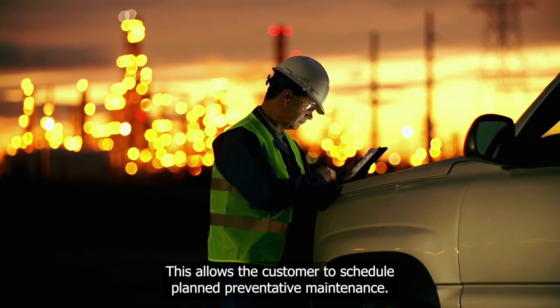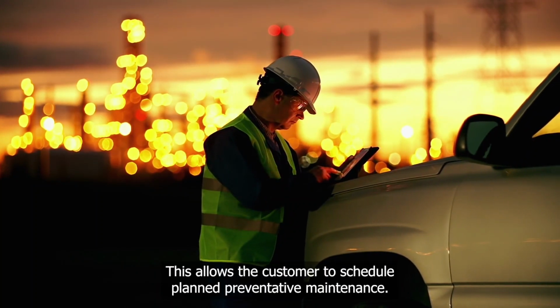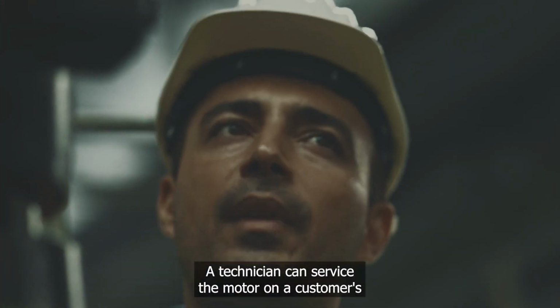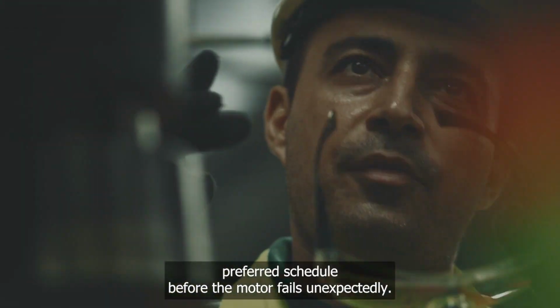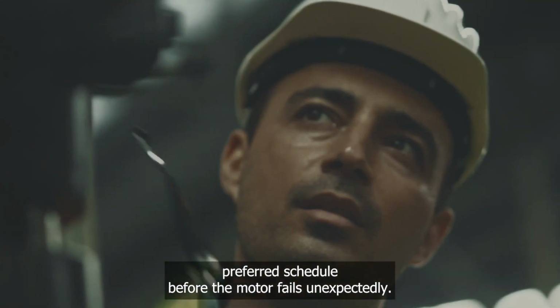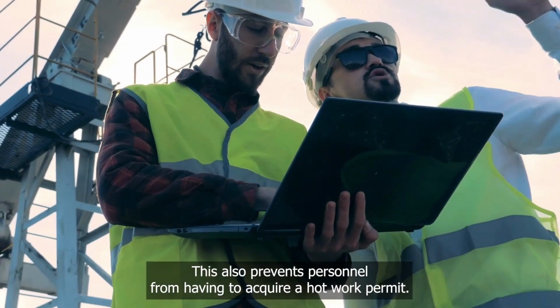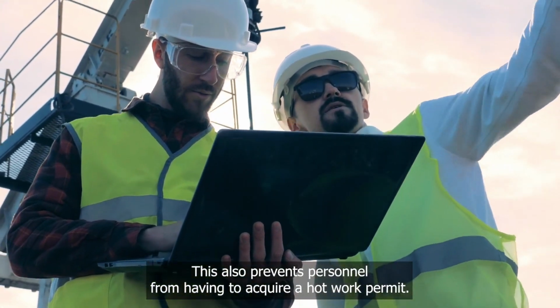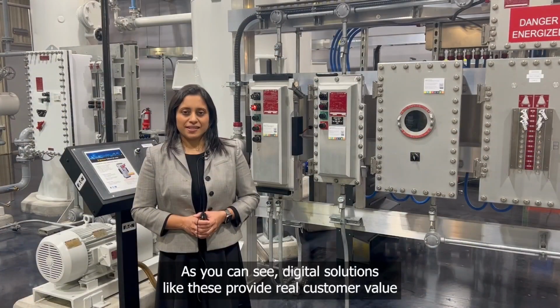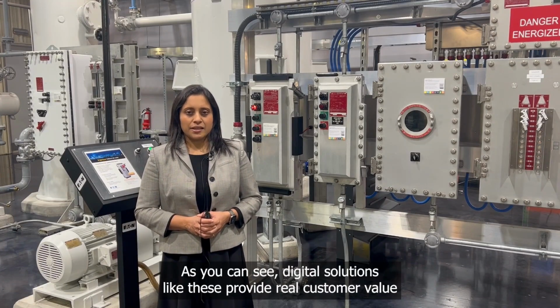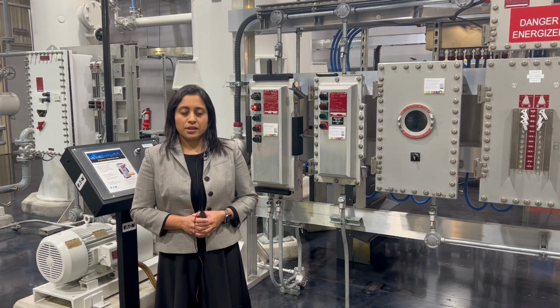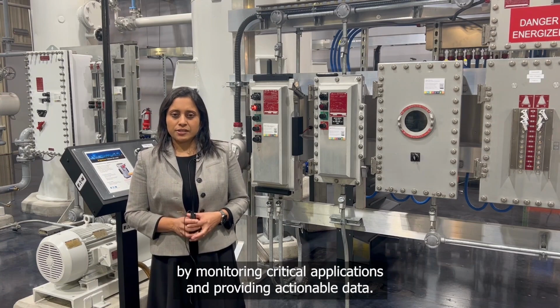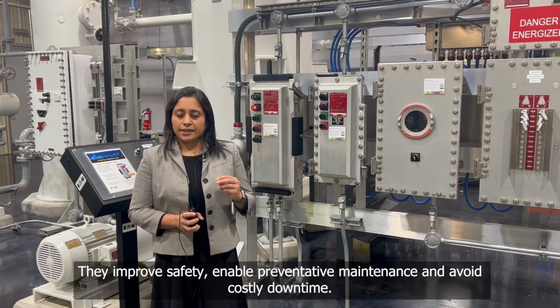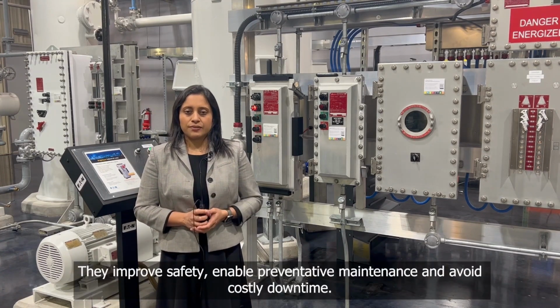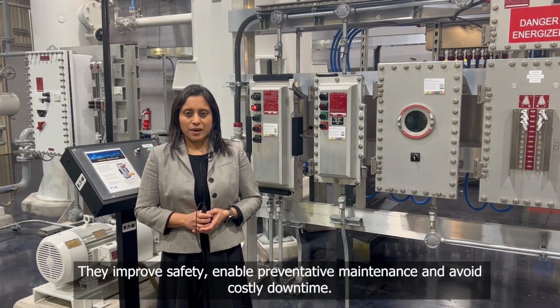This allows the customer to schedule planned preventative maintenance. A technician can service the motor on a customer's preferred schedule before the motor fails unexpectedly. This also prevents personnel from having to acquire a hot work permit. As you can see, digital solutions like these provide real customer value. By monitoring critical applications and providing actionable data, they improve safety, enable preventative maintenance, and avoid costly downtime.